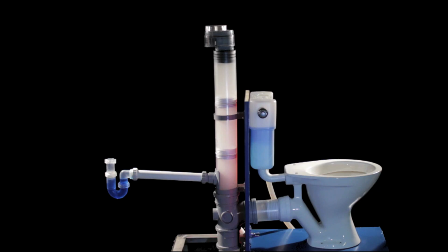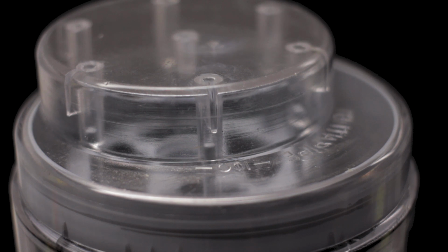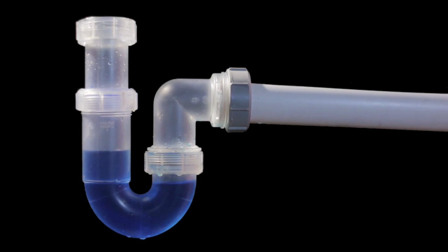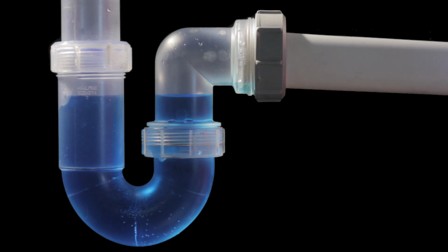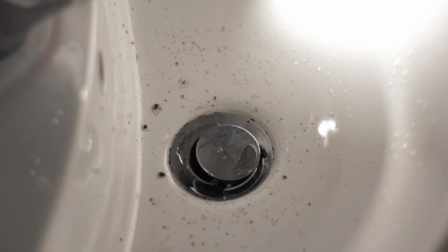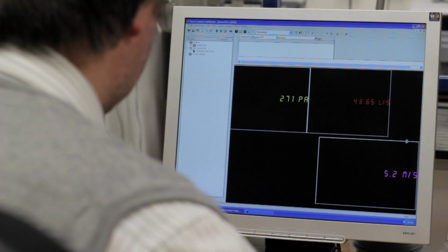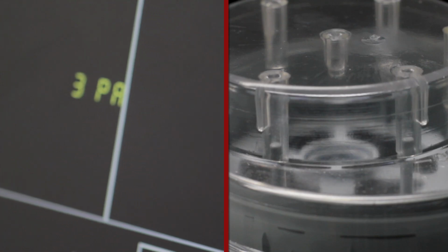An AAV can also act as an advanced warning system against blockages in the building sewer. When the WC is discharged, no air is displaced due to the blockage. This creates positive pressure within the system. The AAV remains closed during positive pressure, so air escapes through the trap. Water and debris are forced up into the sink basin. Water will drain back into the trap, sealing it, and debris left in the basin would highlight the blockage prior to any flooding. McAlpine AAVs are subject to rigorous testing to ensure they comply with European standards.